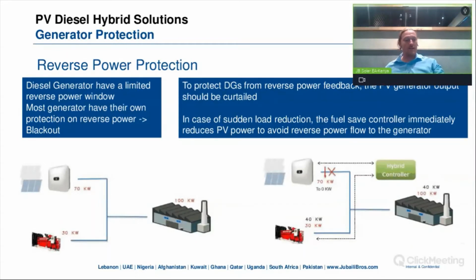So what the fuel save controller does, it is able to curtail the production of the solar panels. It's able to reduce the production of the solar inverter, so that there's no power that goes back into the diesel generator, and you can continue to have power supply to your loads. Again, this is to protect your diesel generator from damage and also to prevent blackouts. The diesel generator will shut off if there's reverse power flow.